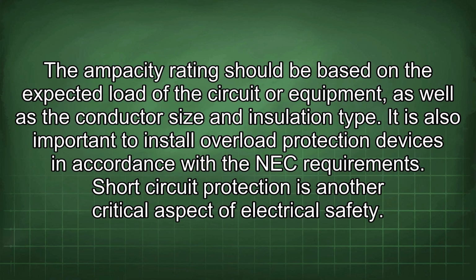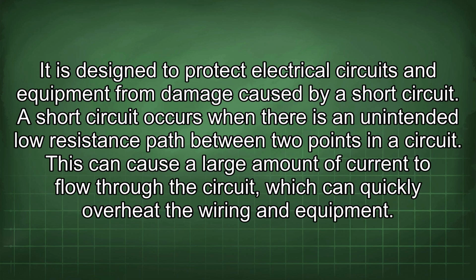The ampacity rating should be based on the expected load of the circuit or equipment, as well as the conductor size and insulation type. It is also important to install overload protection devices in accordance with the NEC requirements. Short circuit protection is another critical aspect of electrical safety. It is designed to protect electrical circuits and equipment from damage caused by a short circuit.